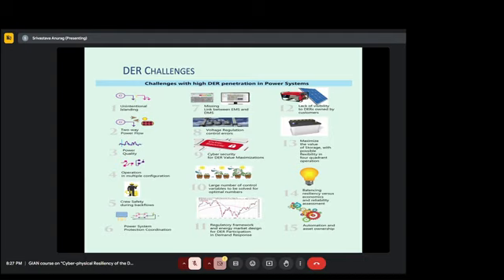Voltage regulation with increasing DER is more challenging, because we typically used to have the voltage be high at the substation feeder and it would go down as more load connected, and we could control that from the feeder. Then we put some cap banks, capacitors, and feed reactive power, basically balancing the reactive power so we get good voltage. But with DERs, when they're feeding their own power and maybe reactive power too, there will be more control variables, and voltage regulation becomes more challenging - how do we set it?